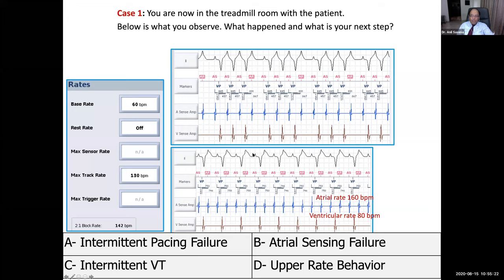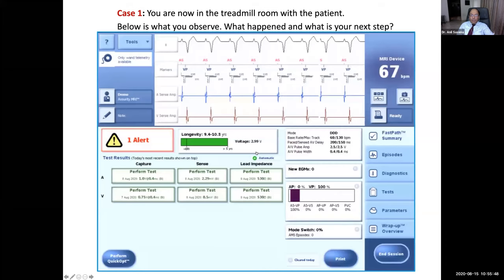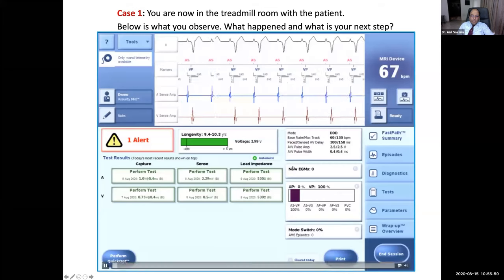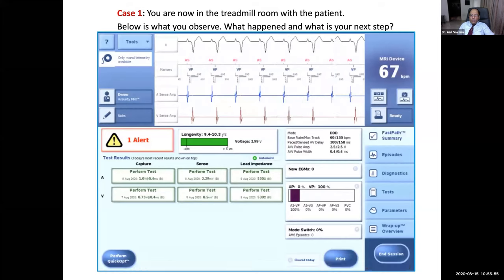Excellent, so it is upper rate behavior, as Dr. Ma has already explained beautifully—in every dual chamber pacemaker we have a lower rate and an upper rate. In this example, the upper rate tracking rate has been programmed to 130. So when we put the patient to exercise, the heart rate gradually increases, and as we can see on this screen, the maximum tracking rate is 130.